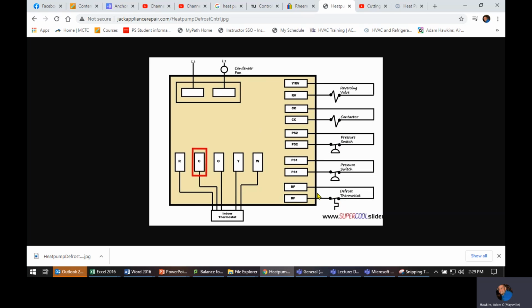So what this stat is doing is it's sensing coil temperature. There's a couple different ways that it can do it, but if it's just a stat, just an open or closed, then that stat is strapped to your outdoor unit coil, just physically strapped to it. And I can show you some pictures here in a little while. And if that thing is strapped to it, it's just going to measure surface temp. So once that thing starts to freeze up, it's going to trip that stat to say, okay, we are in a freezing condition, or potentially freezing, maybe not even freezing, but it is below freezing, so we might need a defrost.